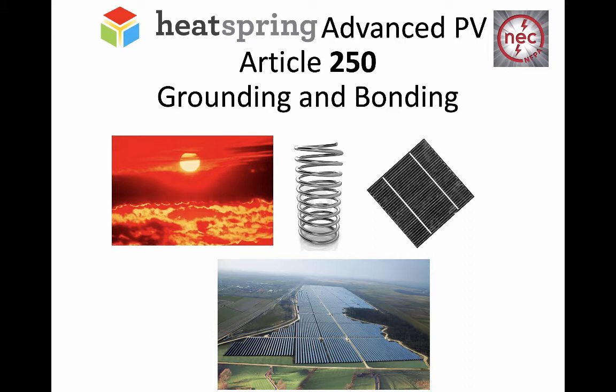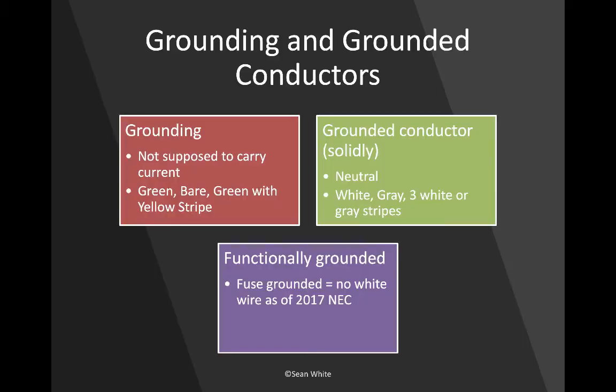We're going to talk about Article 250, Grounding and Bonding of the National Electrical Code. First, let's talk a little bit about some terminology: grounding, bonding, grounded conductors, functionally grounded. Grounding is connecting to Earth, that big thing that we're sitting on right now, and bonding is connecting everything together. However, when we mean bonding, we say grounding all the time, even in the National Electrical Code.